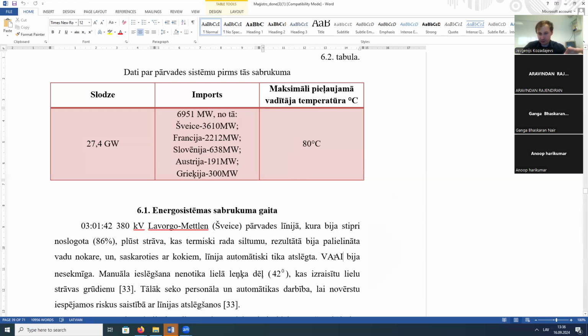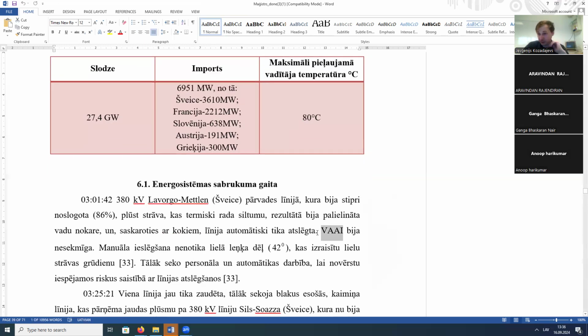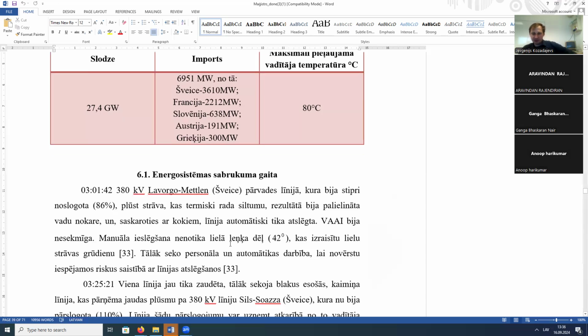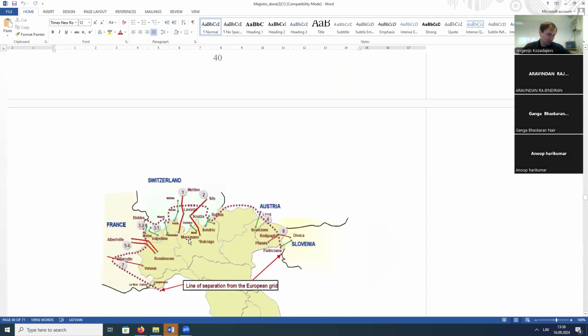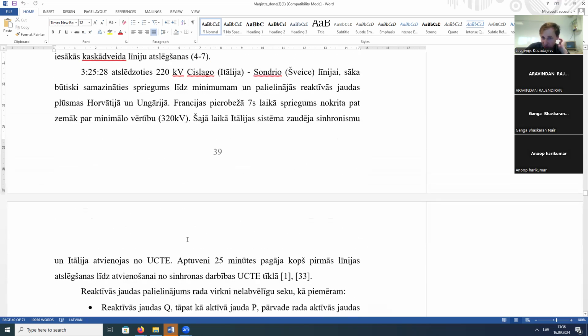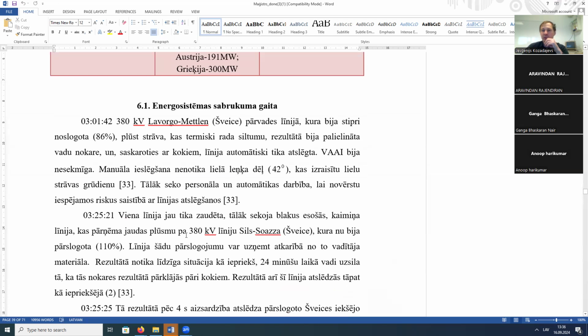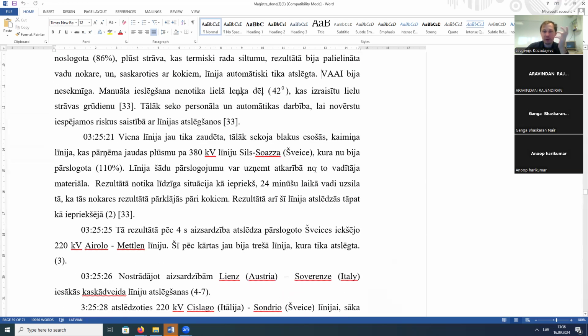As you know from relay protection, there is a recloser, the possibility to reclose. The automation tried to reclose this line back, but without success. These lines are interconnections between different countries, and due to this disconnection, the angle of the EMF vectors from Switzerland and Italy became too big, the angle between the two vectors. As a result, there was no possibility to reclose this line back. So the reclose did not happen. Manually, it was impossible to do this as well.